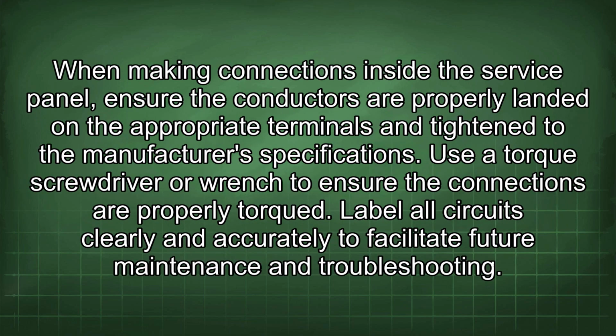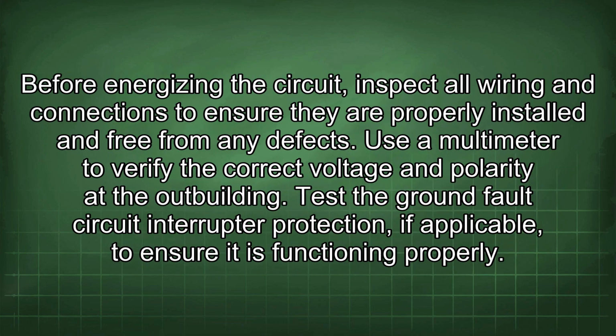When making connections inside the service panel, ensure the conductors are properly landed in the appropriate terminals and tightened to the manufacturer's specifications. Use a torque screwdriver or wrench to ensure the connections are properly torqued. Label all circuits clearly and accurately to facilitate future maintenance and troubleshooting. Before energizing the circuit, inspect all wiring and connections to ensure they are properly installed and free from any defects.